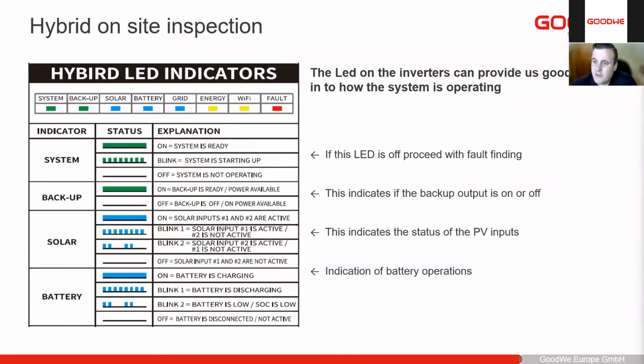So the LEDs of the device generally tell us a lot of what's going on. I won't go through everything individually, as each different device and different model has different meanings for the LED indicators. You'll always find a table like this on the side of the inverter. So when you're on site and you're looking at the LEDs, you can just look at the side of the inverter. There you will find the breakdown, but you also find it in the user manual if it's slightly out of view for you.